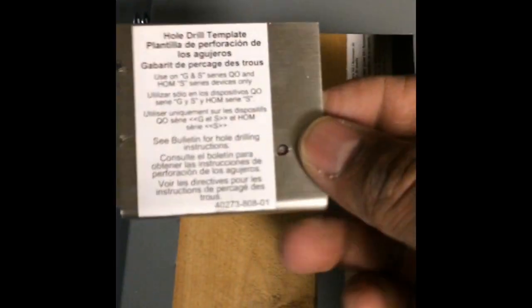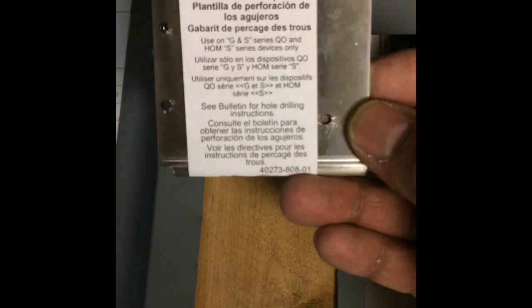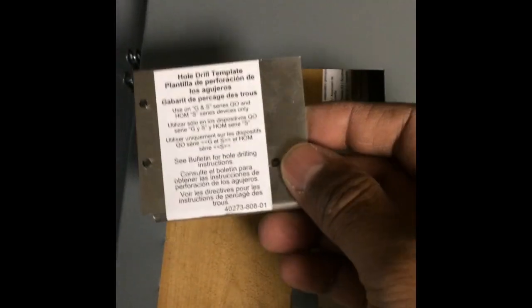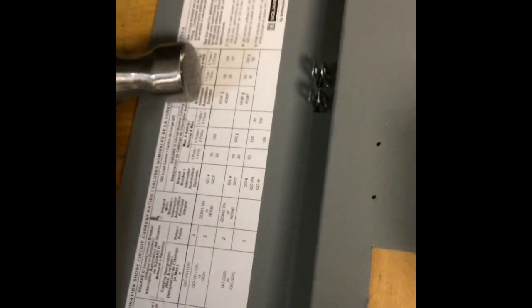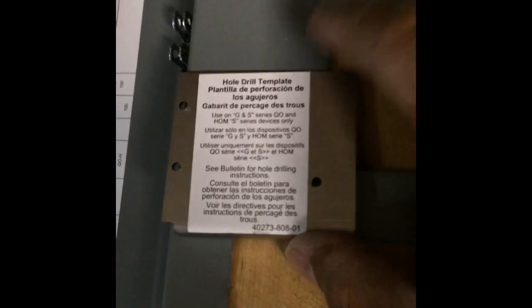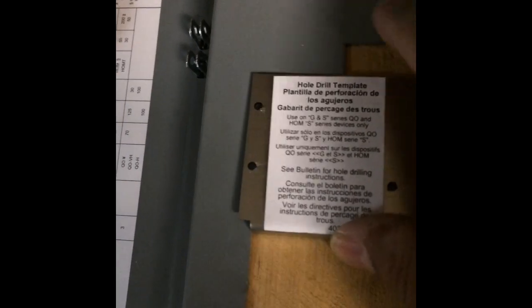Okay, next, Square D provides you with this little drill hole template. You turn your panel cover over. I just stuck a couple of pieces of wood in there. These are like the little 1x4s, so it gives it some stability. What the instructions tell you to do is this is circuit number 2. They want you to put this at the top edge, mark your holes and drill them.